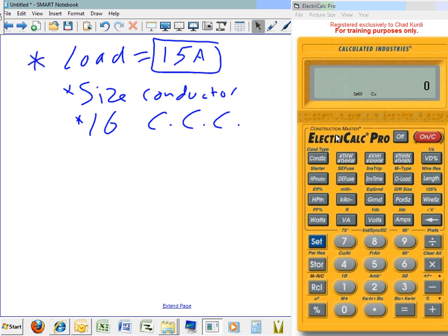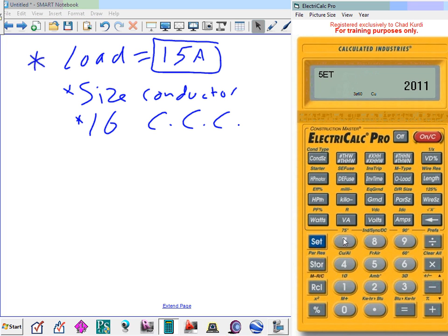Okay, the first thing I want you guys to do is switch your calculator set to 90. Okay, everybody got that one? Everybody set their calculator to 90. So I'm set to 90 copper. Copper is the default. So set 90 will set your calculator to look at the 90-degree column for insulation. Cool? Everybody's okay with that one? Calculator set to 90.